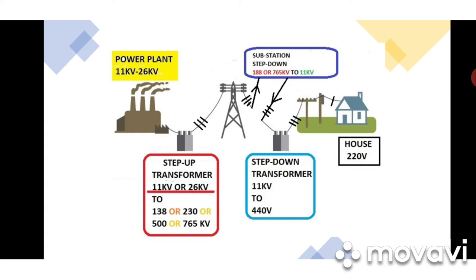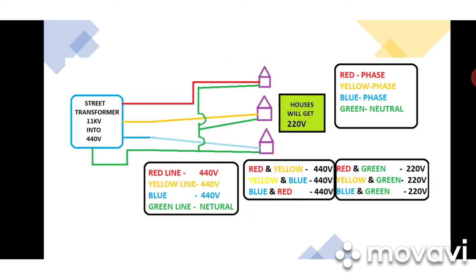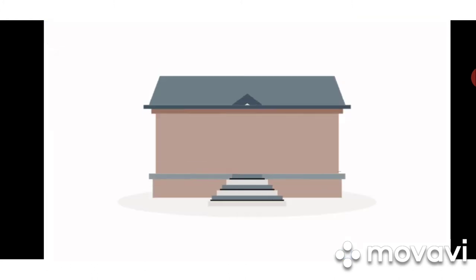They reduce from 11 kV — 11,000 volts — down to 440 volts. From the street transformer, the output comes as three phases: red, yellow, blue, each having 440 volts, plus one neutral also taken from the transformer. Each home gets one neutral and only one phase — not two phases. One phase and neutral together gives 220 volts. This is how you get electricity to your home.